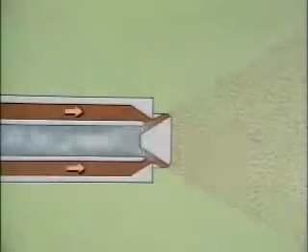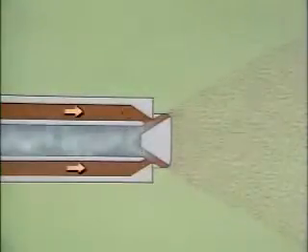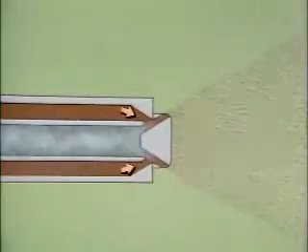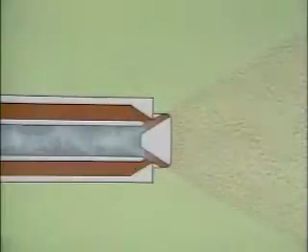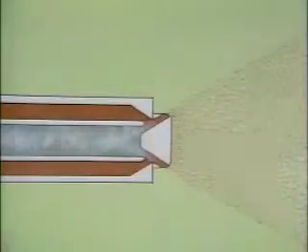Another type of atomizer can use either steam or air to atomize oil. Steam or air flows through a tube and then to a nozzle in the sprayer head. Oil is supplied through the atomizer to the sprayer head, which directs the oil into the path of the high-velocity steam or air. This breaks the oil into a fog-like mist as it enters the combustion area, making the oil easier to ignite and burn.